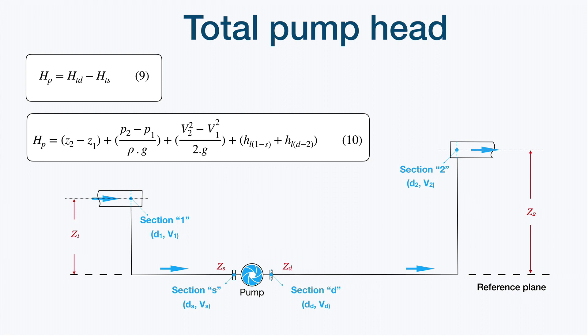The energy the pump must add to the system covers the difference in geodetic head between points 2 and 1, the difference in pressure energy between points 2 and 1, the difference in kinetic energy between sections 2 and 1, and the pressure losses between sections 1 and 2. This is the pump head the pump must add to cover the energy needs of the system. In the next lesson, we will recall how to determine pressure losses for straight pipes, accessories, and valves. Goodbye!